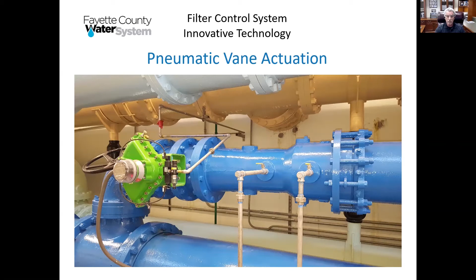That's it, the only electrical connections. No 3-phase power, no single-phase power. The airline coming into it is the power. We don't need all the other wires for monitoring and control because that's all eliminated by those 2 wires. Interestingly, those same 2 wires on an AS-i bus network provide the power to those solenoids on the side of the actuator, so we don't need another pair of wires to power them up. The power and the I/O for monitoring and control is all contained within an AS-i bus network. Simple, simple, simple.